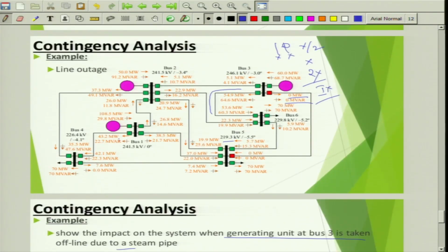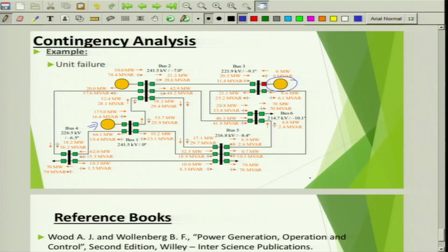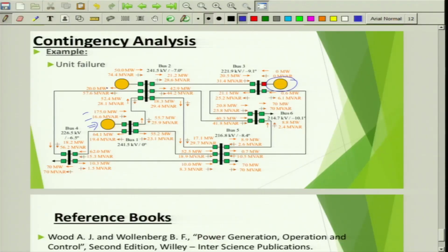Earlier this was generating some 108.5 megawatt and 29.8 MVAR. Now because this generation of 60 and 68 is gone, it is shifted to this generator. That is why you can see here that now this has increased to 175 and 16 point something like that. So there is a change. You are intentionally giving a command to this specific slack generator, assuming this is a slack generator. You give this command and increase its generation so that you meet the expectation. This is how you manage, or you can also collectively divide among the different generators.